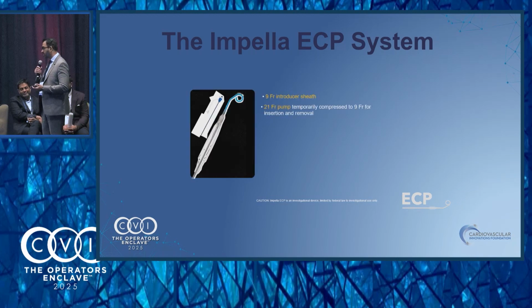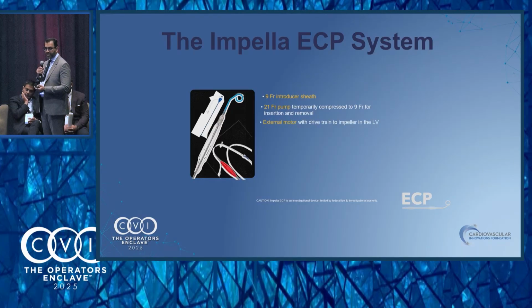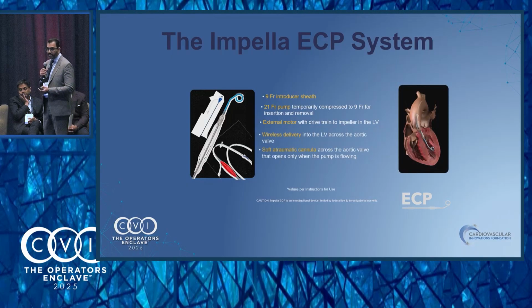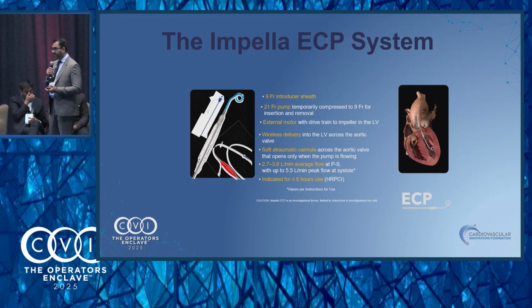came into place, because the concept was to shrink the device into a 9 French introducer sheath. The device itself is temporarily compressed. The pump itself is a 21 French with an external motor drive to the impeller in the LV. It's a wireless delivery system, unlike the CP, which you cross across the valve. It has a soft atraumatic cannula. I will share a clinical case. The device itself has shown 2.7 to 3.8 liters of average flow, with up to 5.5 liters of peak flow in systole.